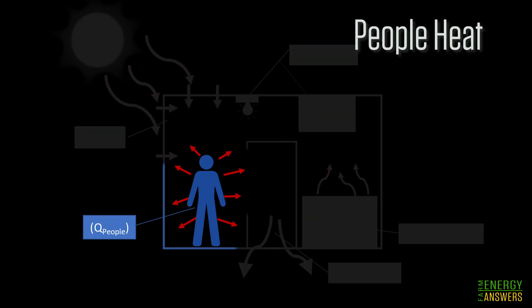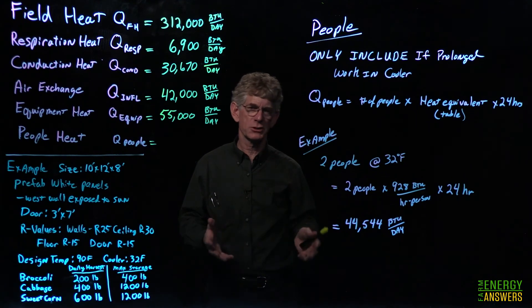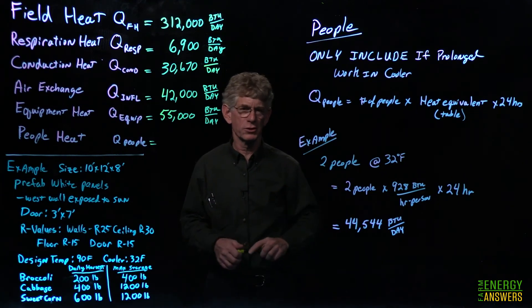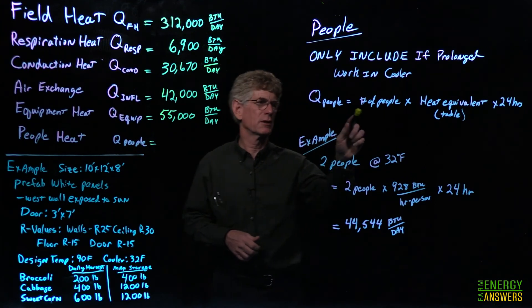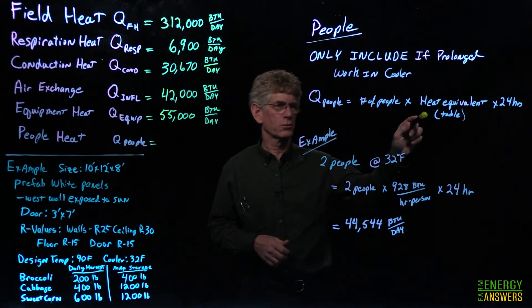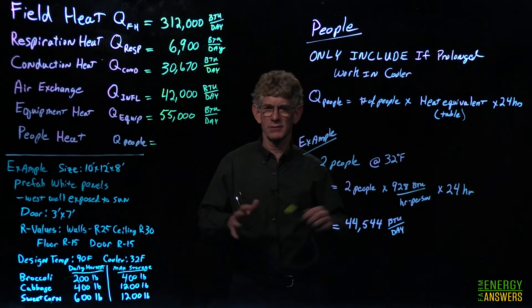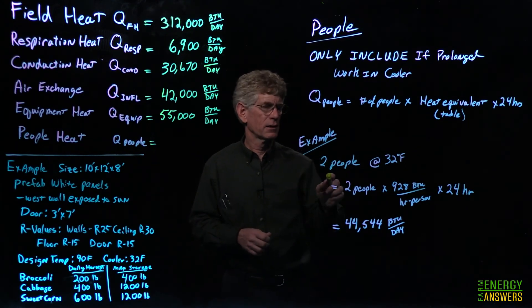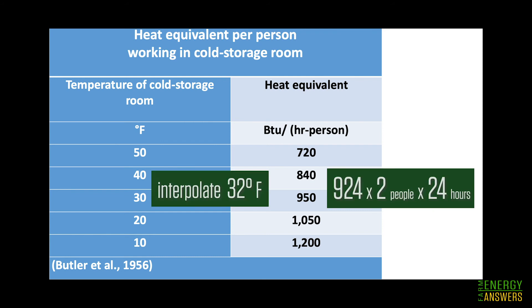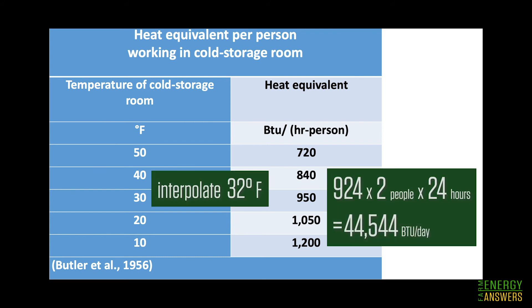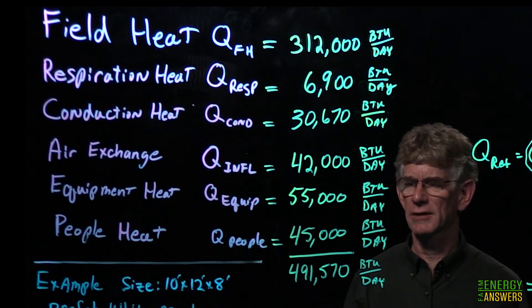People heat load is only included if people are working in the cooler for a prolonged period — sorting, packaging, not just briefly entering and leaving. The formula is: number of people × heat equivalent (from table) × hours. At 32°F, the table gives approximately 45,000 BTUs per day for two people working in the cooler.